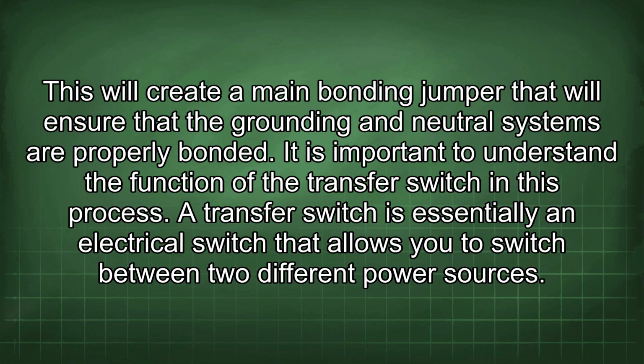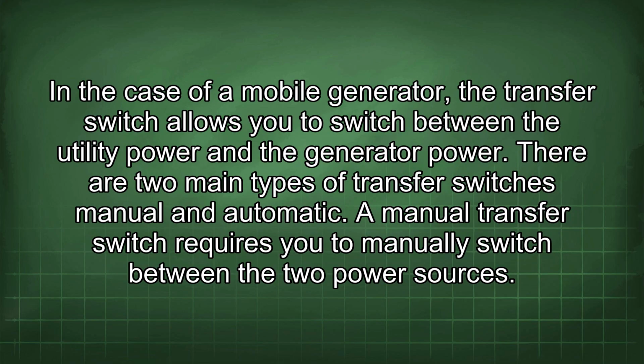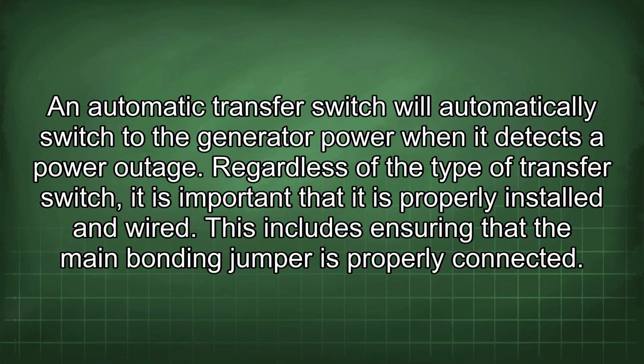A transfer switch is essentially an electrical switch that allows you to switch between two different power sources. In the case of a mobile generator, the transfer switch allows you to switch between the utility power and the generator power. There are two main types of transfer switches: manual and automatic. A manual transfer switch requires you to manually switch between the two power sources. An automatic transfer switch will automatically switch to the generator power when it detects a power outage. Regardless of the type of transfer switch, it is important that it is properly installed and wired. This includes ensuring that the main bonding jumper is properly connected.